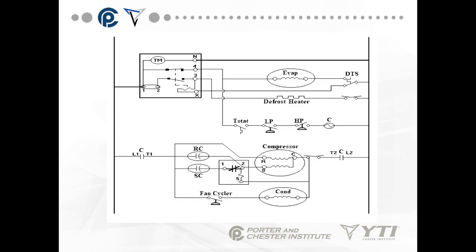This is one example of a refrigeration wiring diagram. This area up here on the left is a commercial defrost time clock. It has a clutch solenoid in it, right where my mouse pointer is, and it has pins 1, 2, N, 4, 3, and X. X goes to the termination side of my defrost thermostat. Pin 4 is my evaporator fan and my compressor contacts. My compressor and condenser are here, controlled on a contactor, which is labeled C.